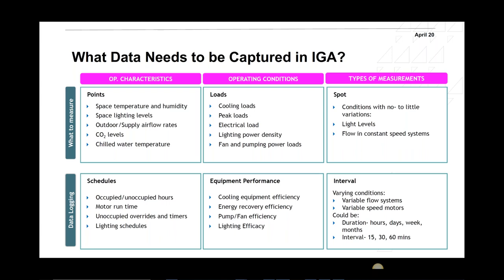It could be performing properly, and then the measurement is just assuring us that it's working properly or not. Pumps and fan efficiency: what is the watt per liter per second for the pump or for the fan? Lighting efficacy: what is the watt per lux level? So comparing lighting equipment, or lighting bulbs, to others or fixtures.